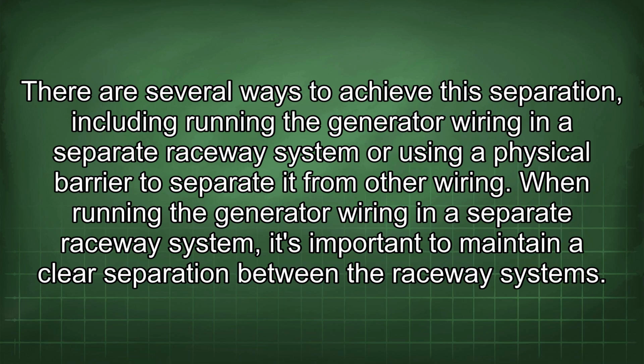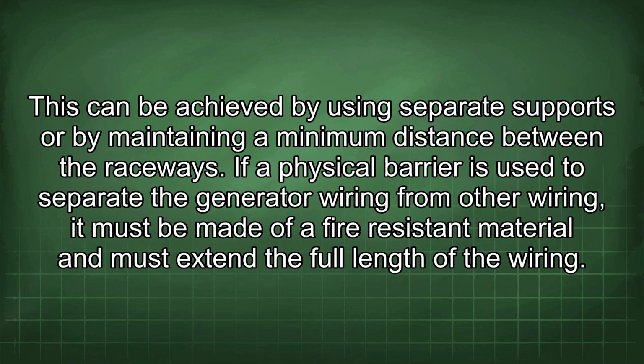When running the generator wiring in a separate raceway system, it's important to maintain a clear separation between the raceway systems. This can be achieved by using separate supports or by maintaining a minimum distance between the raceways. If a physical barrier is used to separate the generator wiring from other wiring, it must be made of a fire-resistant material and must extend the full length of the wiring.